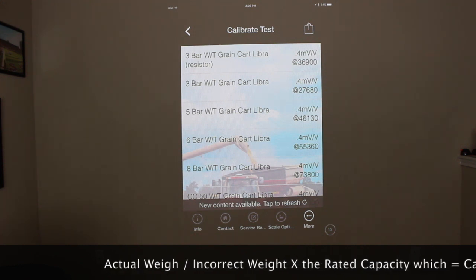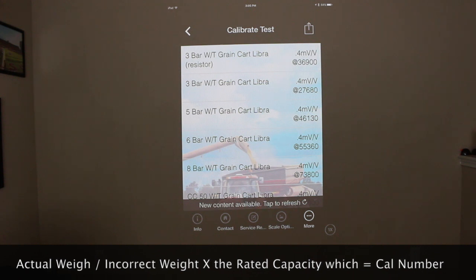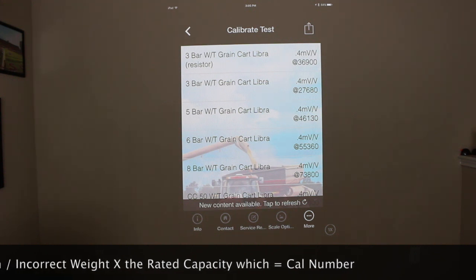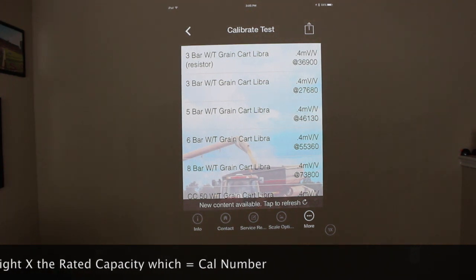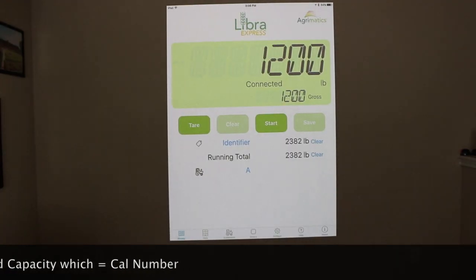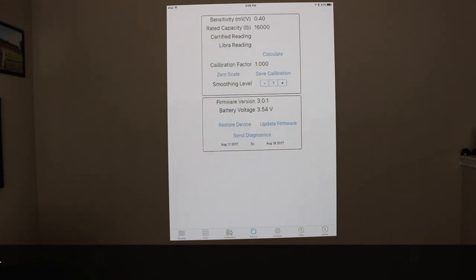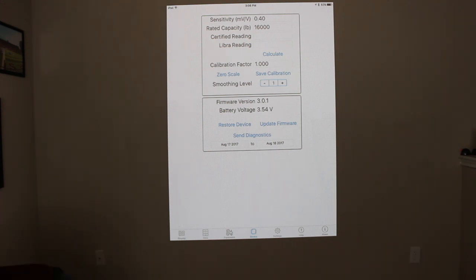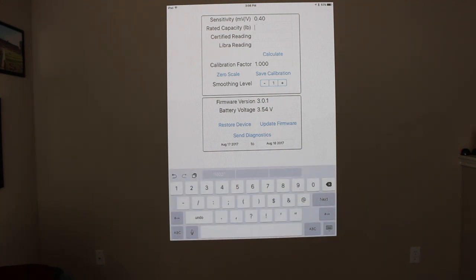But I will have the calibration formula available for you at the bottom of the screen. So in continuation with the calibration, you see the formula is on the bottom of the screen. So I go to the device tab, and let's say that I do have a 3-bar grain cart without the resistor, and I'll go through and change this to 27,680, and I'll save the calibration from there.